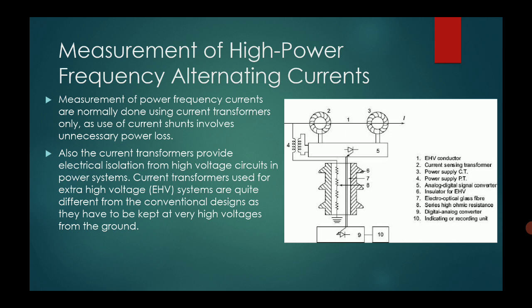Now we discuss measurement of high power frequency alternating currents. The schematic diagram is shown on the right-hand side. Measurement of power frequency currents is normally done using current transformers only, as use of a current shunt involves unnecessary power loss. Current transformers also provide electrical isolation from high voltage circuits. In power systems, current transformers used for extra high voltage (EHV) systems are quite different from the conventional design, as they have to be kept at a very high voltage from ground.